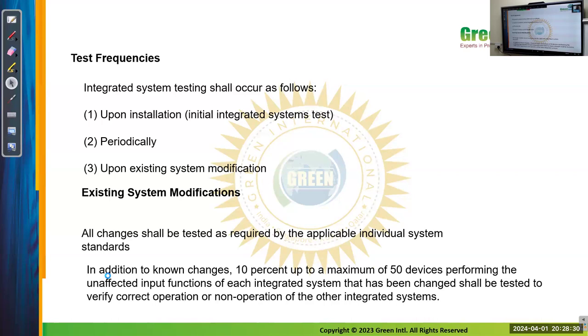So, integrated test frequencies. Test frequencies shall have the following things. There are three types of testing. One is upon installation: after the installation is done, we will do the entire test. Then it will be periodic. There is a testing frequency for each of the systems. We have studied NFPA 25, right? In all the parts there is ITM, inspection, testing, and maintenance, with a frequency for all the testing. So integrated testing shall be done periodically based on the schedule.